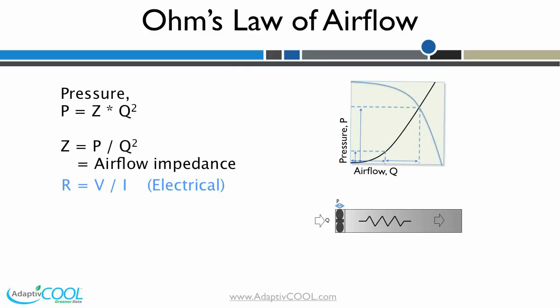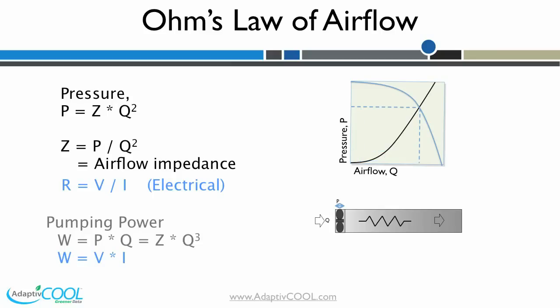It only takes 25 percent of the pressure to drive 50 percent of airflow. This relationship between pressure and airflow is clear from the equation and the plot. Pumping power — the power required by a fan to push air — is the product of airflow and pressure, or P times Q. This is similar to P equals V times I in the electrical domain.